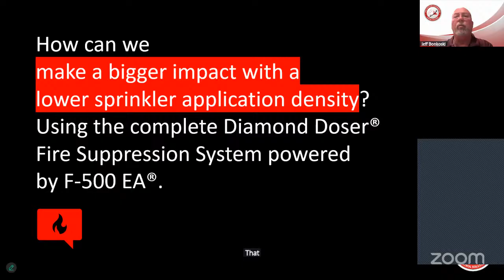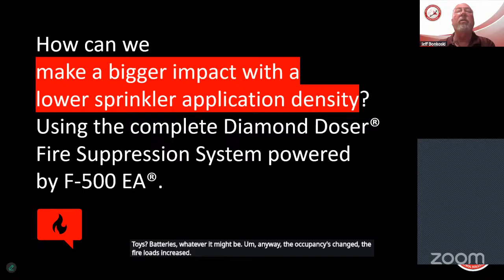So now let's look at how we can get F500 into our sprinkler systems, looking at sprinkler densities. Those older distribution centers or warehouses that maybe 10, 15, 20 years ago had a sprinkler density sufficient for the codes of the time and the occupancy they were used for. But since then, the load has changed with more modern toys, batteries, whatever it might be. The occupancies changed, the fire loads increased. Does that system still meet today's codes? Do we need to rip the entire system out, or can we add something into the existing system to help bring it up to or even exceed today's standards?